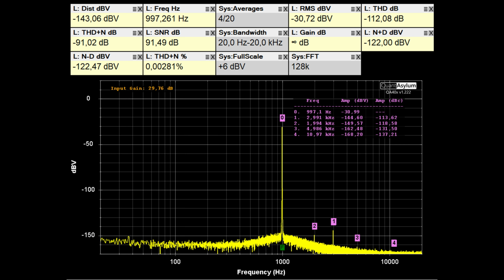So you understand fully the method. In fact, the software allows you to run a frequency response test, which will create the weighing file, which you see displayed on screen as weighing. And this is the difference. Here is without the weighing file being applied. And so you have minus 30 dB, exactly minus 29.76 dB to apply to get the results. In fact, you see when you calculate, there is a slight difference of less than a dB, 0.70 dB, and that's what the weighing adds for precision.